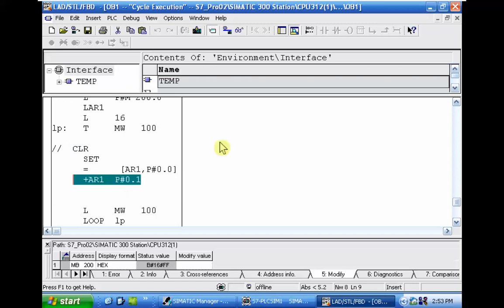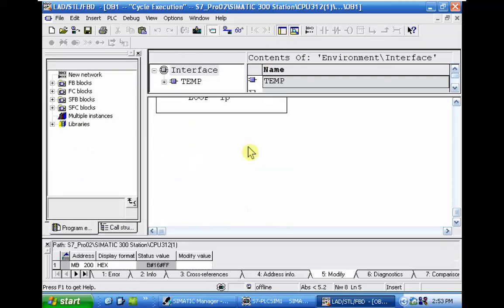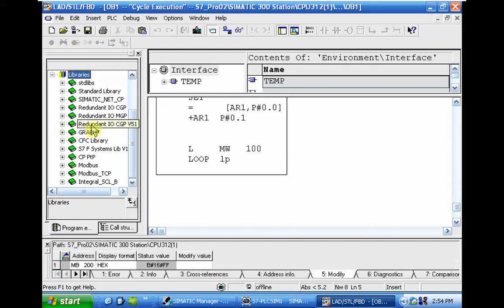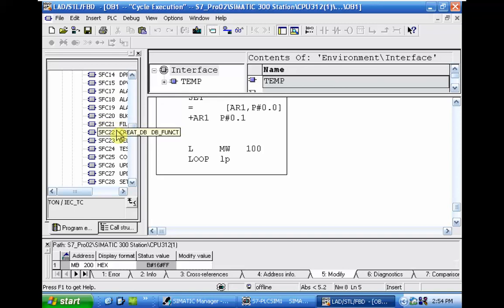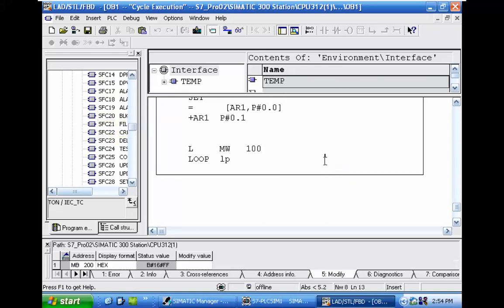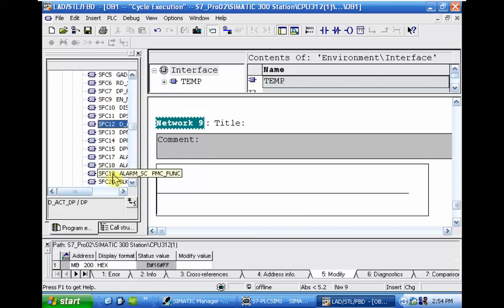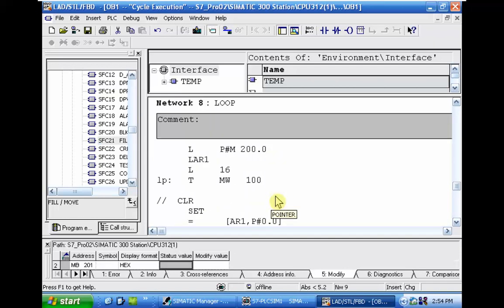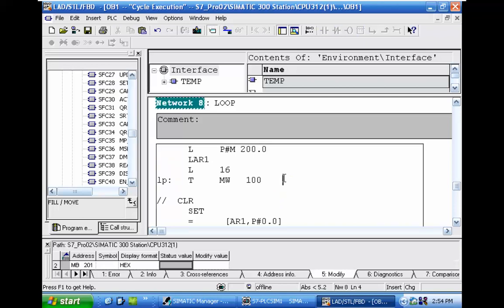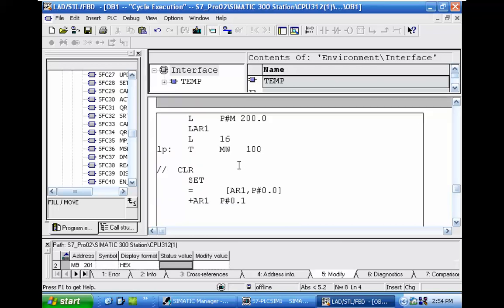This cannot be directly converted to ladder because it's a complex STL program. We have a pointer section, a loop section, loop initialization, setting the first memory, incrementing the address, and then moving to the next iteration. This concept cannot be copied to ladder one by one, but there is a system function available in ladder from the library. If you go to system functions, SFC21 will do the same thing — SFC21 will fill a memory area.